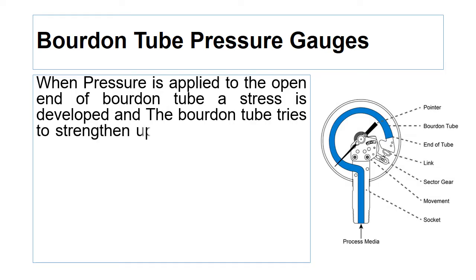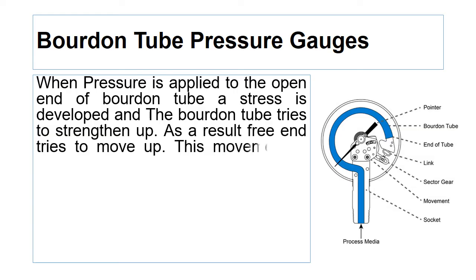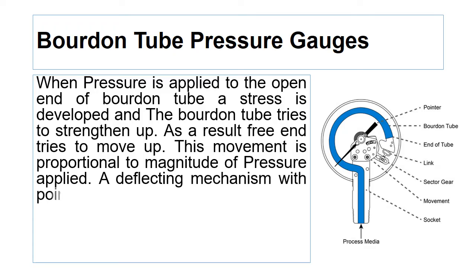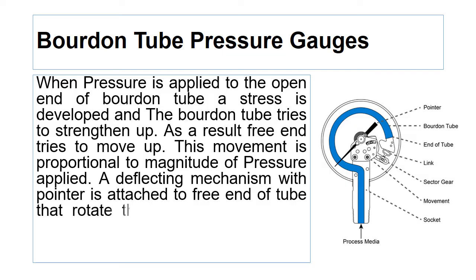As a result, the free end tries to move up. This movement is proportional to the magnitude of pressure applied. A deflecting mechanism with a pointer is attached to the free end of the tube, which rotates the pointer on a calibrated scale. The pointer indicates the reading of the pressure to be measured.